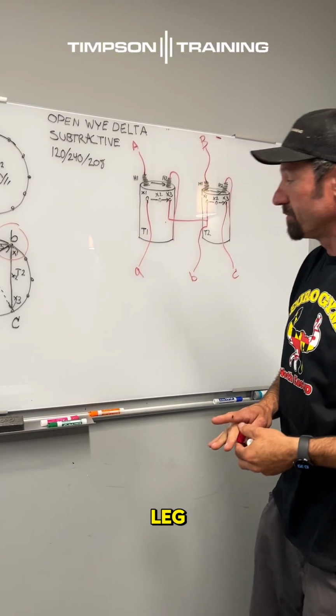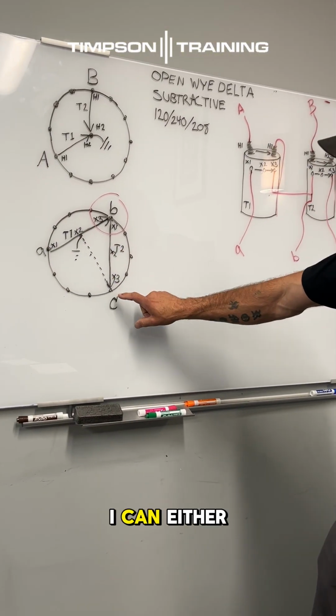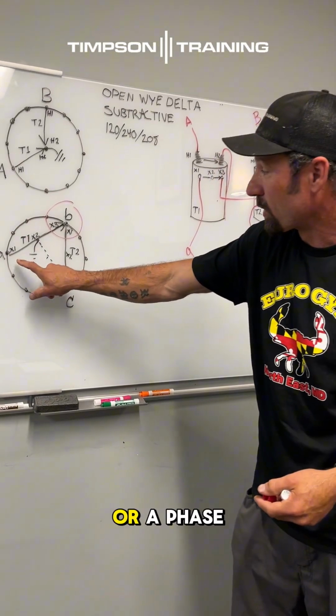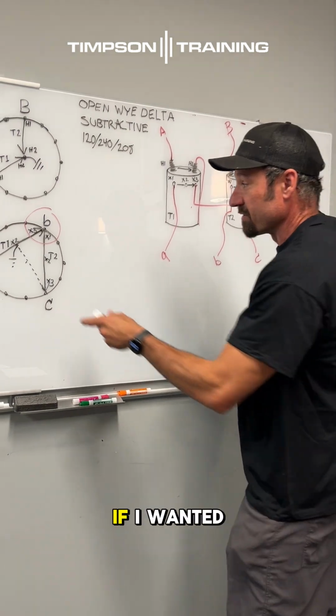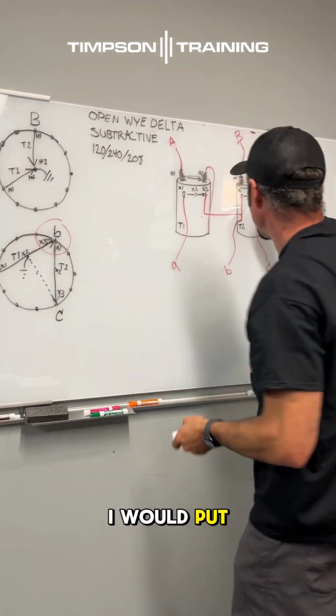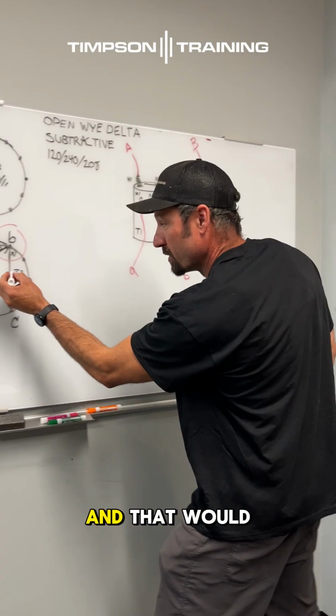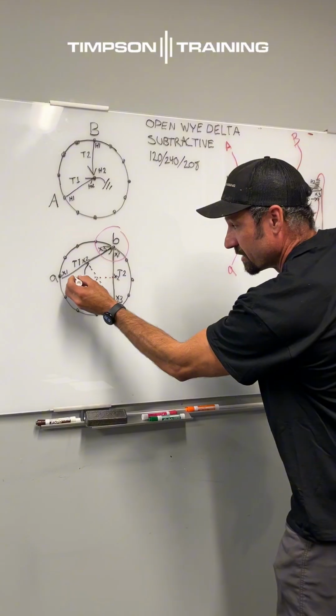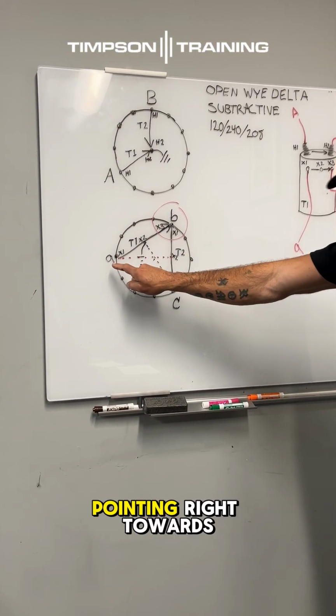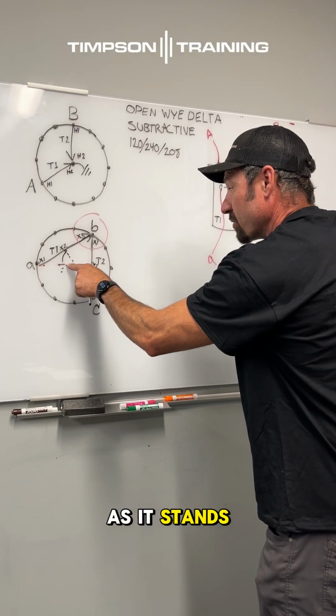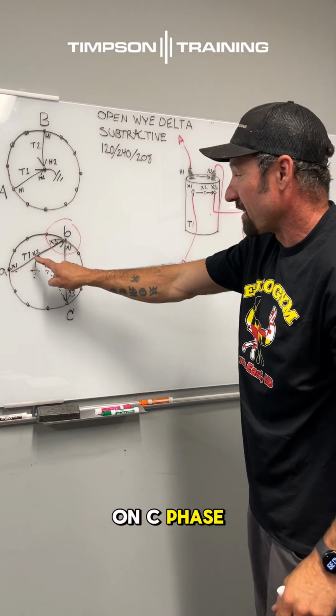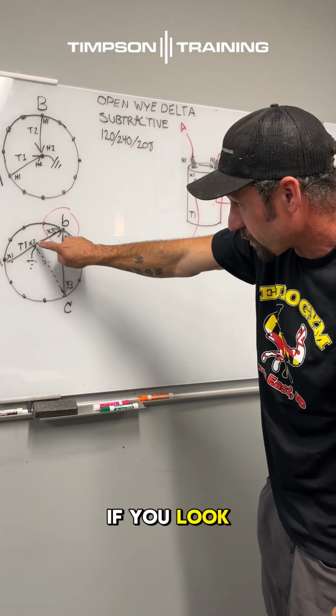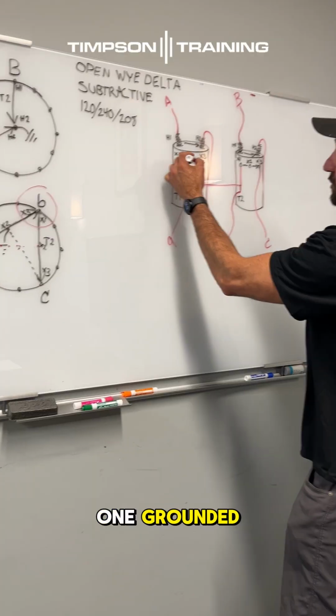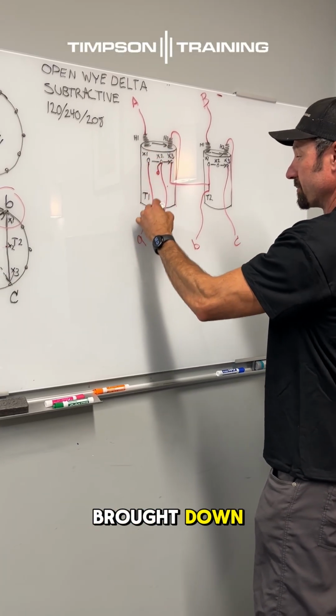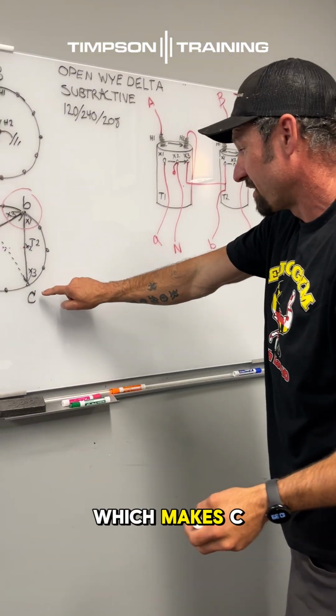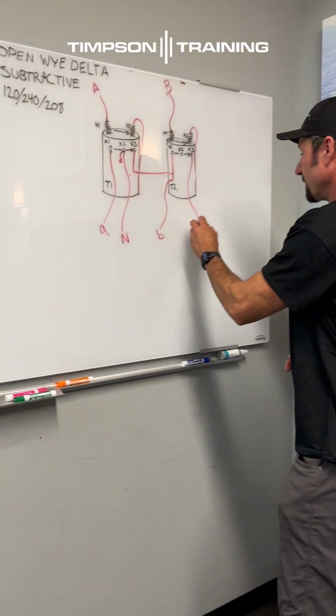Now let's look at the high leg. On this transformer configuration, I can either have the high leg on C phase or A phase. It cannot be B phase though. If I wanted the high leg to be A phase, I would put my ground on transformer 2 and that would look like this. And you can see that dotted line's pointing right towards A phase, but as it stands, we have it drawn on C phase. So it looks on this vector, if you look here, I have my X2 of transformer 1 grounded and a neutral brought down, which makes C phase the high leg.